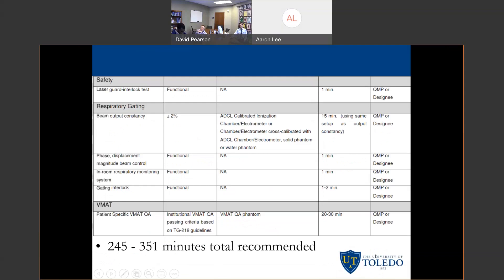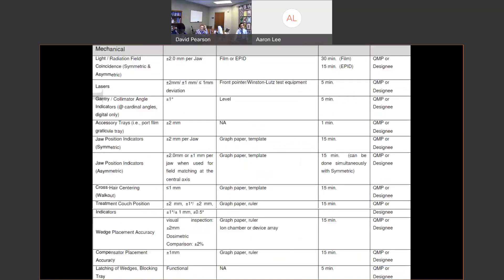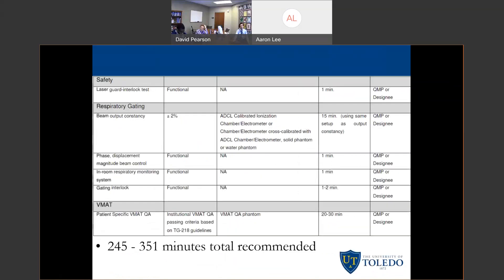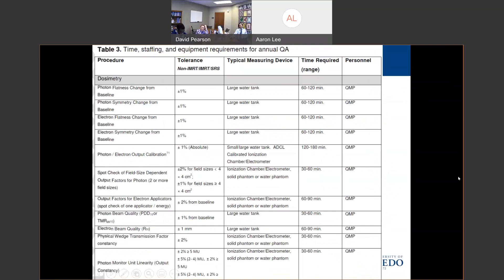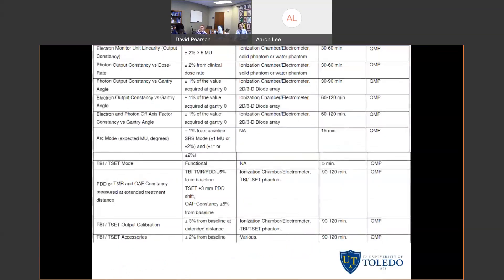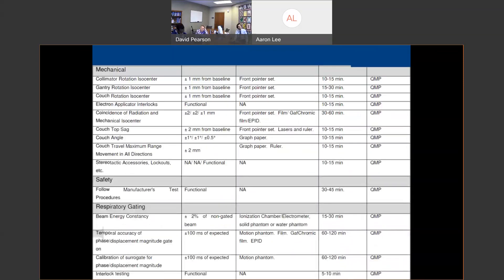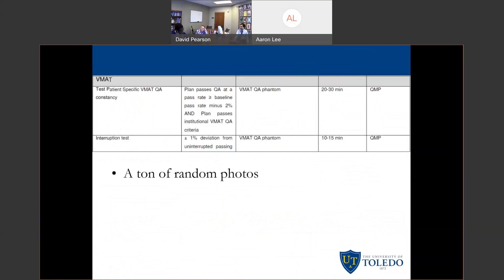For the annual table, they talk about using a large water tank for most things, and if you have an ion chamber array you can use that as well. They specify that annual QA must be performed by the QMP — if you have a resident or assistant trained by the QMP, they should not be the sole person doing annual; the QMP should be present and performing all of the annual QA. They again break down the time for all these tests, and they quoted approximately 40 to 200 hours depending on how complex your machine is. There are also some images in the report of various QA devices, though they are somewhat randomly placed and not all labeled.